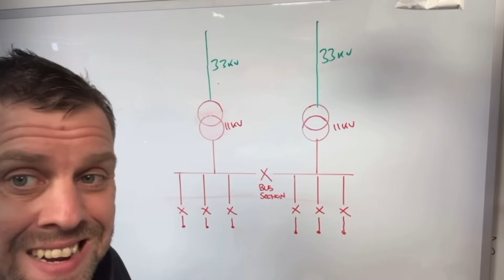We've got a 33 kV supply coming in, and a second 33 kV supply coming in. As you can see, they come from two separate sources and are not connected on the 11 kV side - there is nothing joining these together. They are separately fed 33 kV incomers. How your area works may vary, they might have a bus section on their side, I don't know - everything's different.